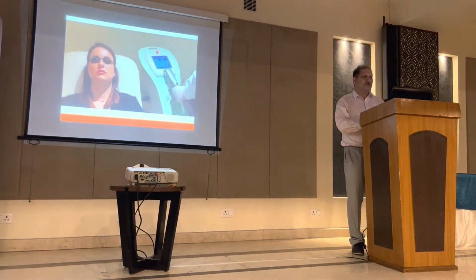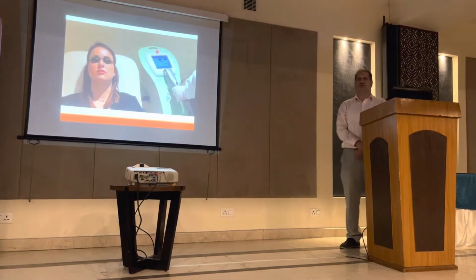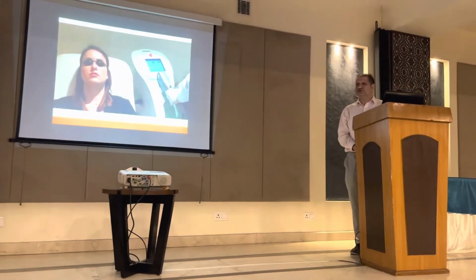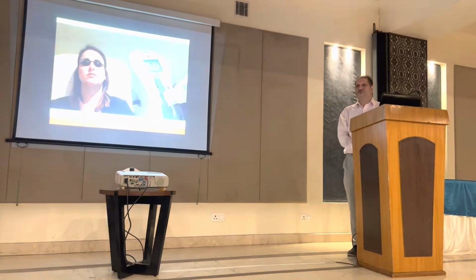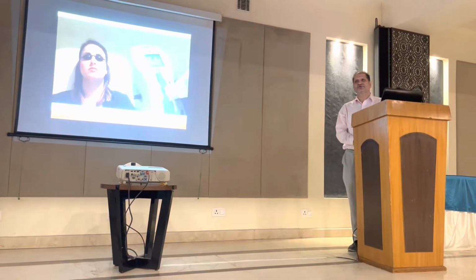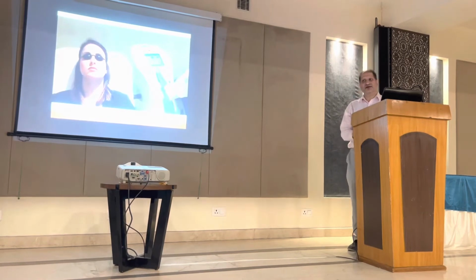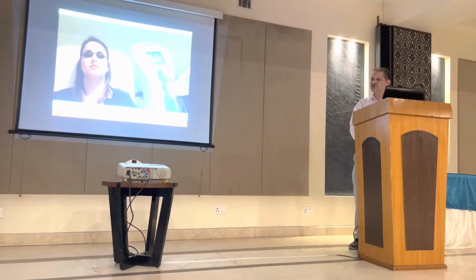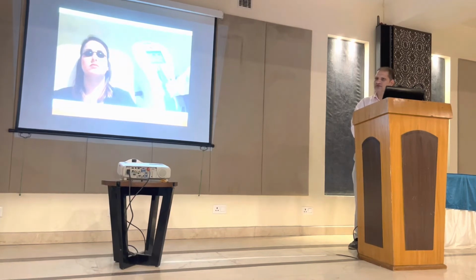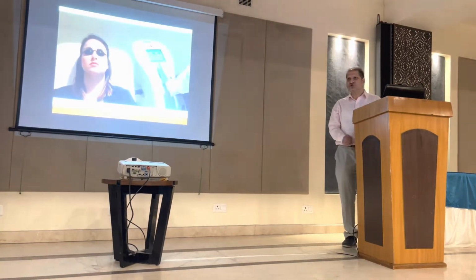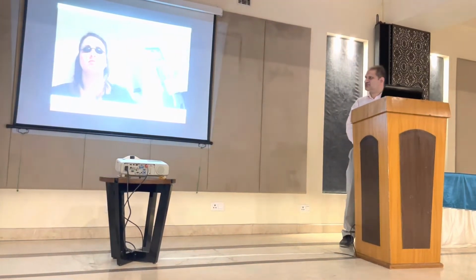So the important thing here is that both the patient and the person who is doing it should wear the goggles, because the protective goggles are very important. The intense pulse light can be absorbed by the pigment in the eye, like uvea. It can cause anterior iritis, it can cause pupillary distortion, or it can be absorbed by the RPE and cause retinal damage. So the goggles are very important to be worn by both the examiner and the patient. So this is one more video.